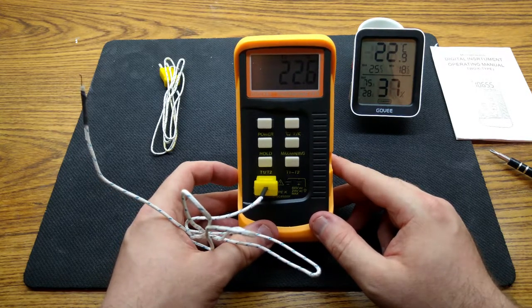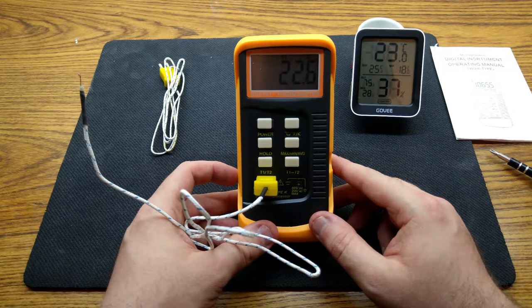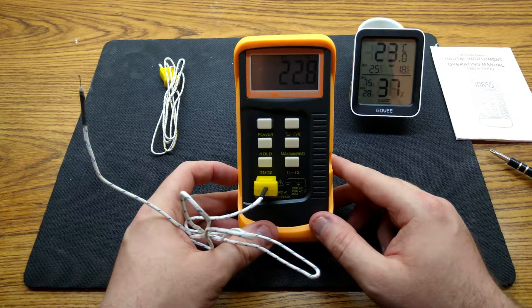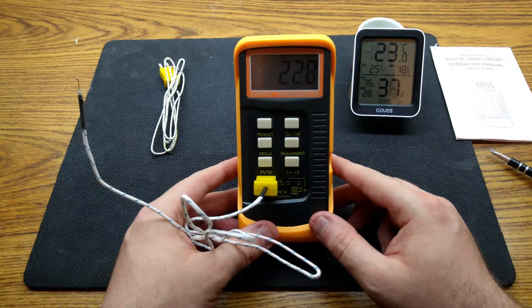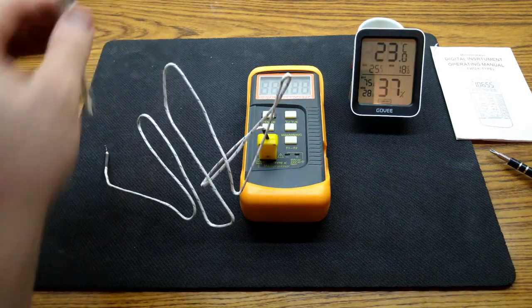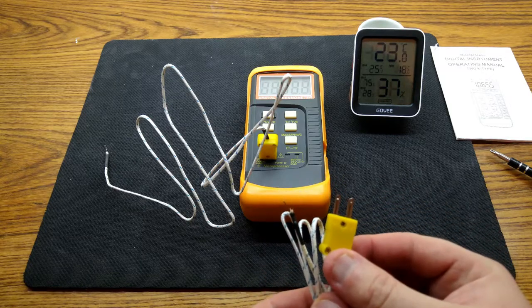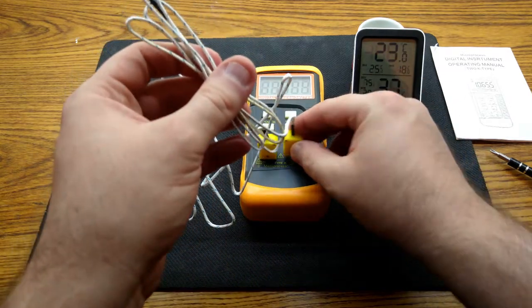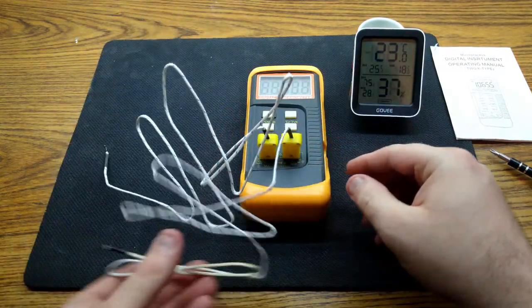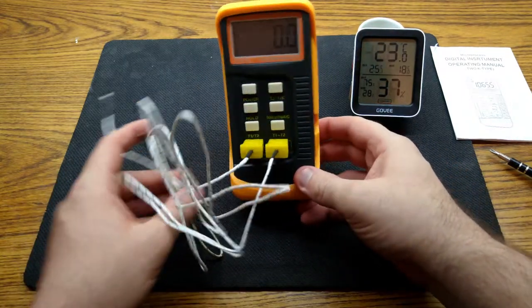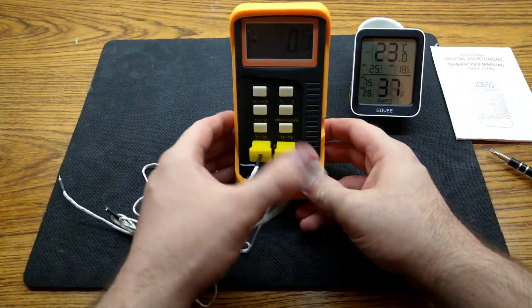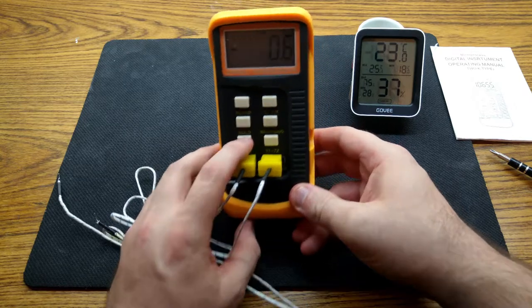This is especially considering the unit is stated as having an accuracy of between plus and minus 0.5 degrees Celsius. If I go ahead and plug in the second thermocouple, we can see that it also gives an accurate value when compared to the Govee, and that the T1 minus T2 setting is working as expected.